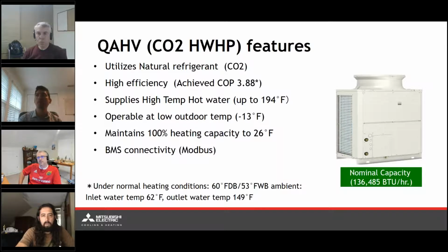But to your question as to the COPs and heating capacities in low ambient conditions, I don't quite have the info yet. I've been screaming for it, and as soon as I do get it, I promise that I'm going to be going on and on and on about it. All right, but as you said, these are rated 100% of heating capacity down to 26 degrees. If other City Multi equipment is to go off of, the derates that start at that point are steady, and it's not an exponential decay. It's rather just a flat slope from 26 degrees down to negative 13. So in Boston design conditions, on design day, I'd be comfortable saying that I anticipate between 70 and 80% of your heating capacity in those temperatures.